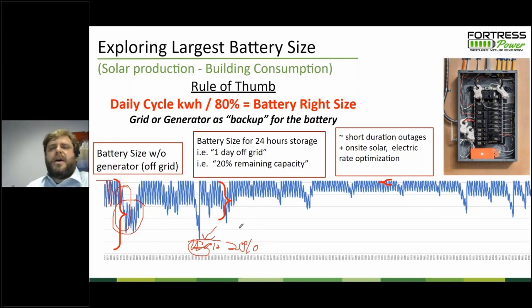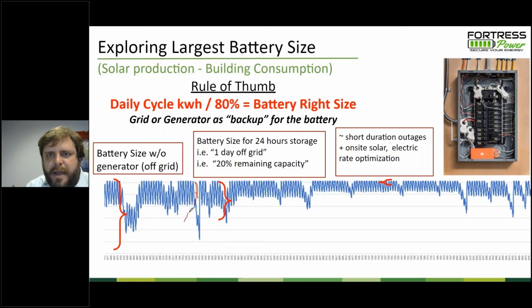And then if you go with a generator, you could say, okay, during this time frame, I'm going to have my generator click on, and that's going to get me back up to the top here. And so I run my generator at that time, and now my graph looks normal, and we avoid this period. And so for lithium ion with a generator battery bank, instead of having 3 or 4 days' worth of storage, I might just look at what my load is during my heaviest period of use. That could be the summertime, that could be the wintertime, but I might look at what my 1 day of heavy use is and then have 20% remaining, and then say anything below that, that's a time when my generator is going to kick on and play free safety.